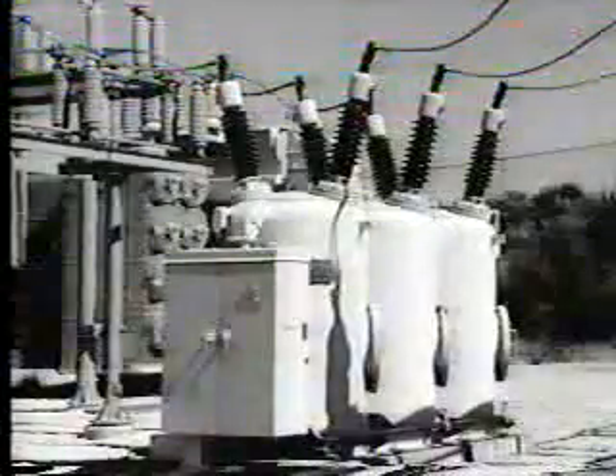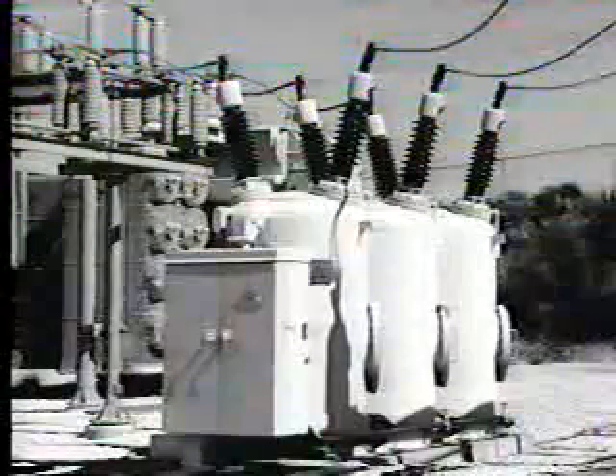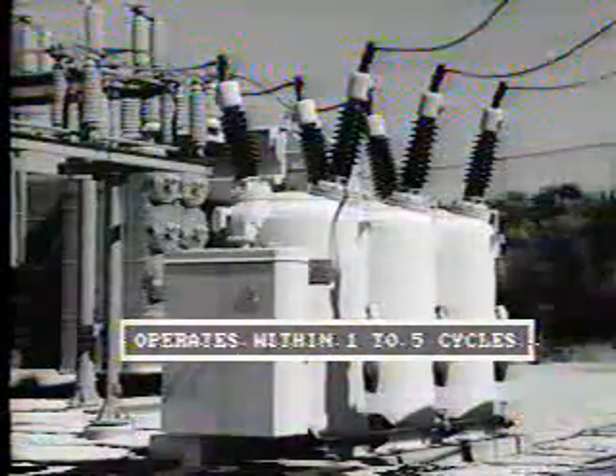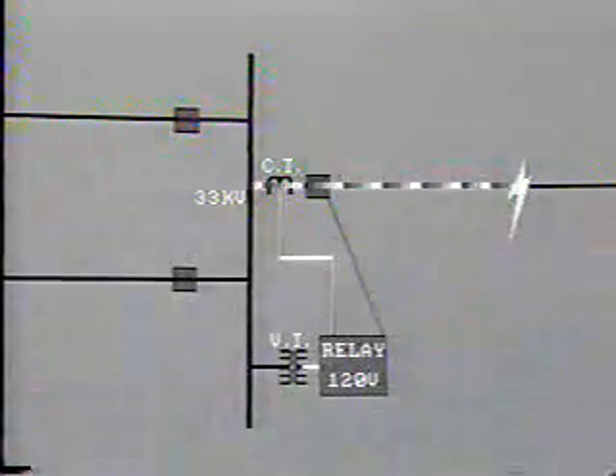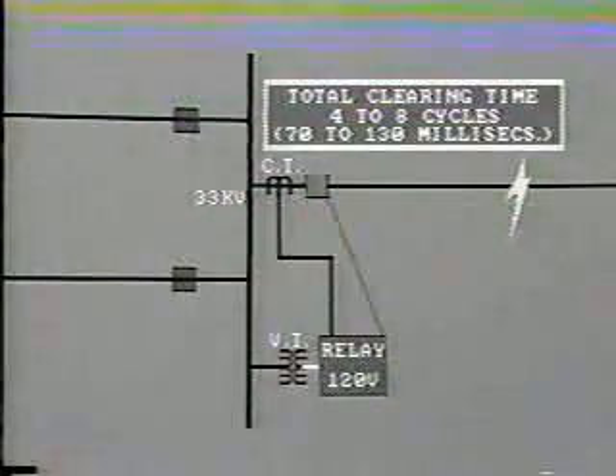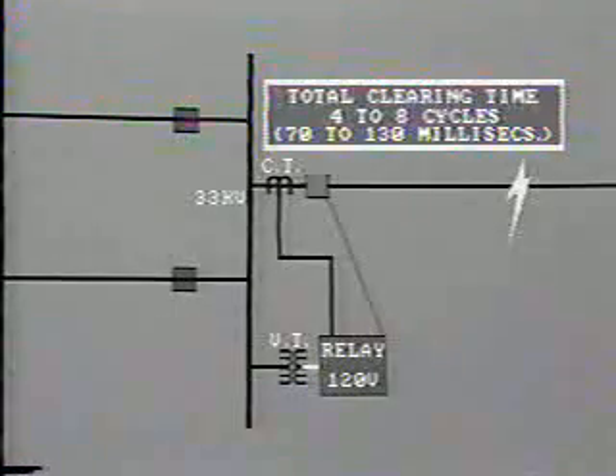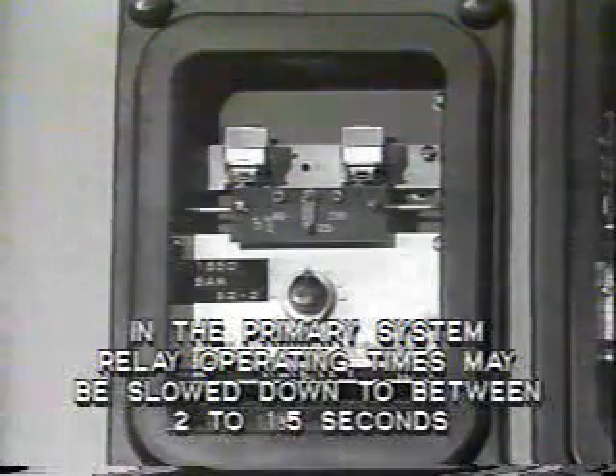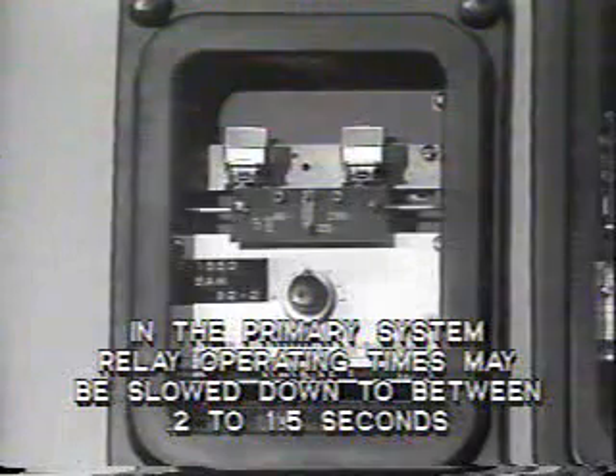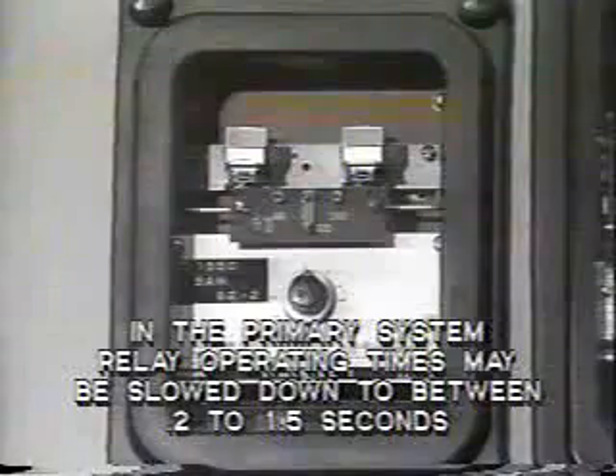The terms high-speed relay and instantaneous relay are often used interchangeably. This means a relay which operates within 50 milliseconds, that is, 3 cycles. But in opening a circuit, we also have to consider the operating time of the circuit breaker. In general, modern circuit breakers operate within 1 to 5 cycles. So we can say that the total clearing time, that is, the relay operation plus the breaker, ranges from about 4 to 8 cycles, that is, 70 to 130 milliseconds. But high-speed relays are not always desirable. Time coordination is often required between protective relays to allow them to operate in the correct sequence. For example, in the primary system, relay operating times may be slowed down to between 0.2 to 1.5 seconds.